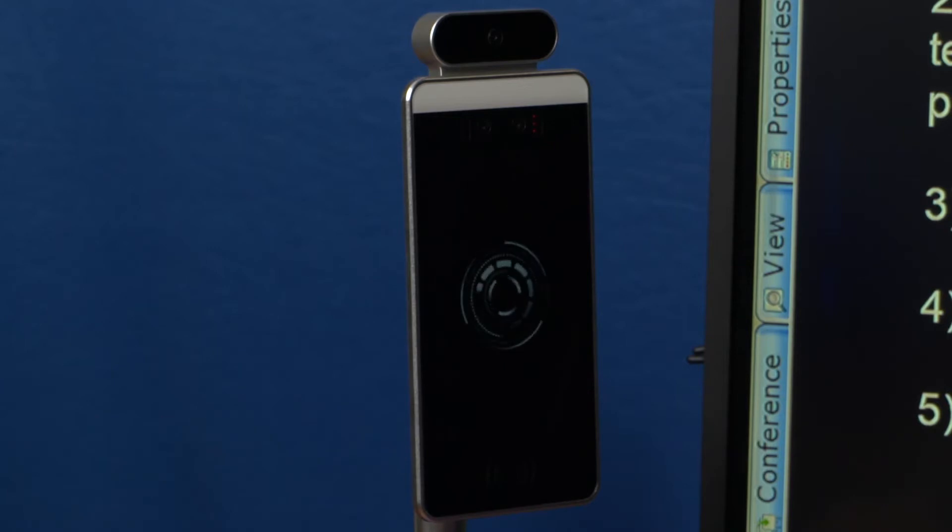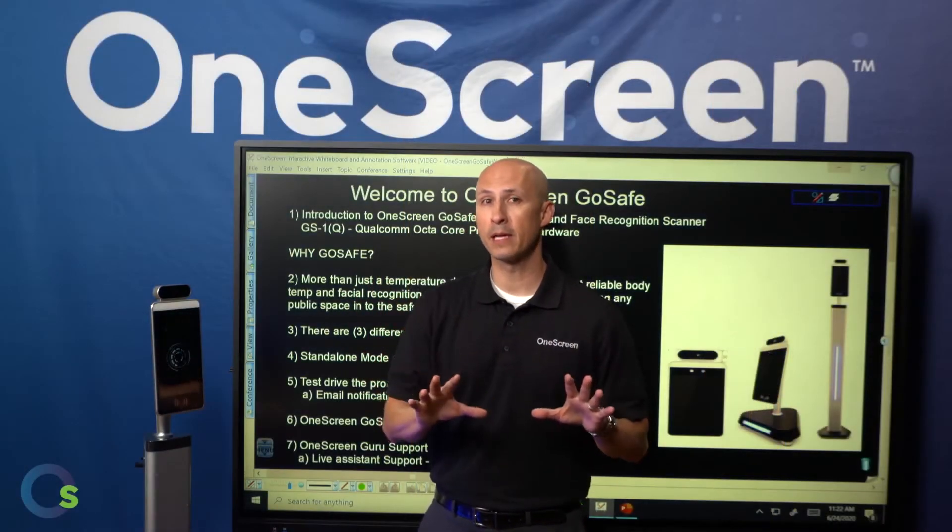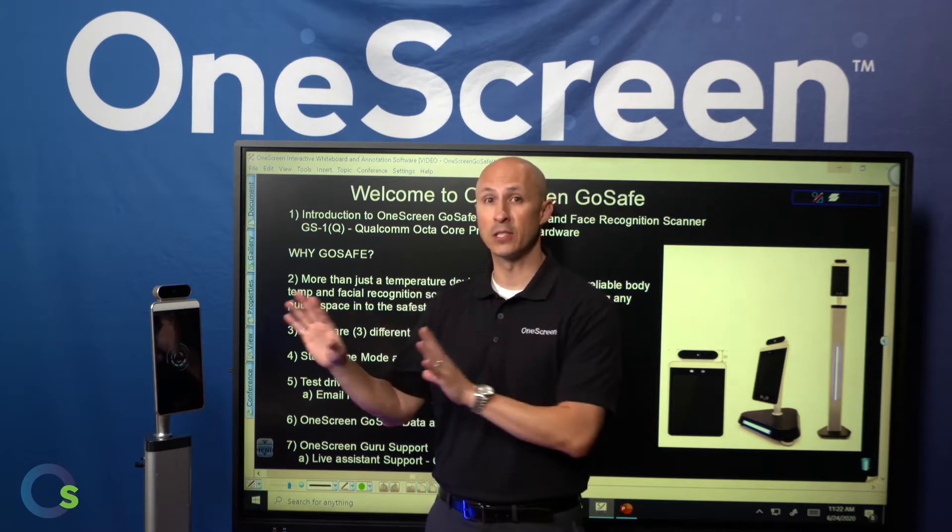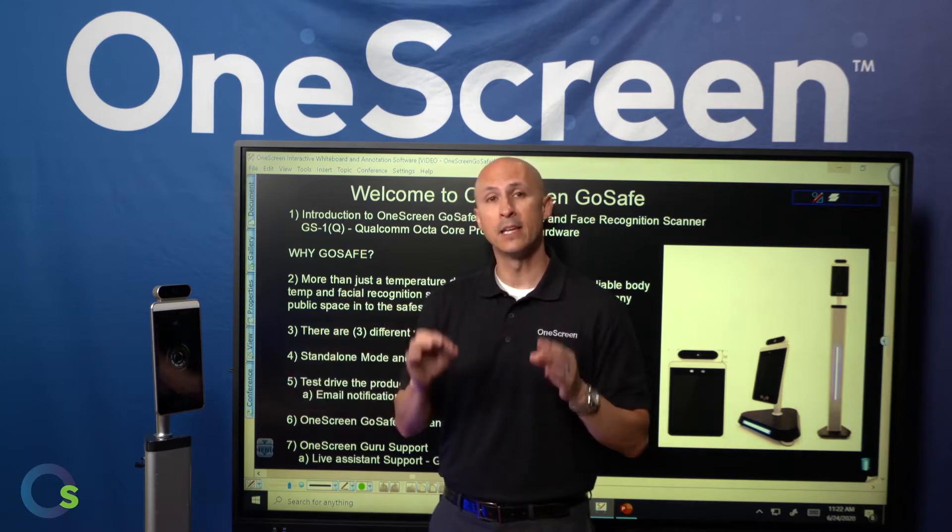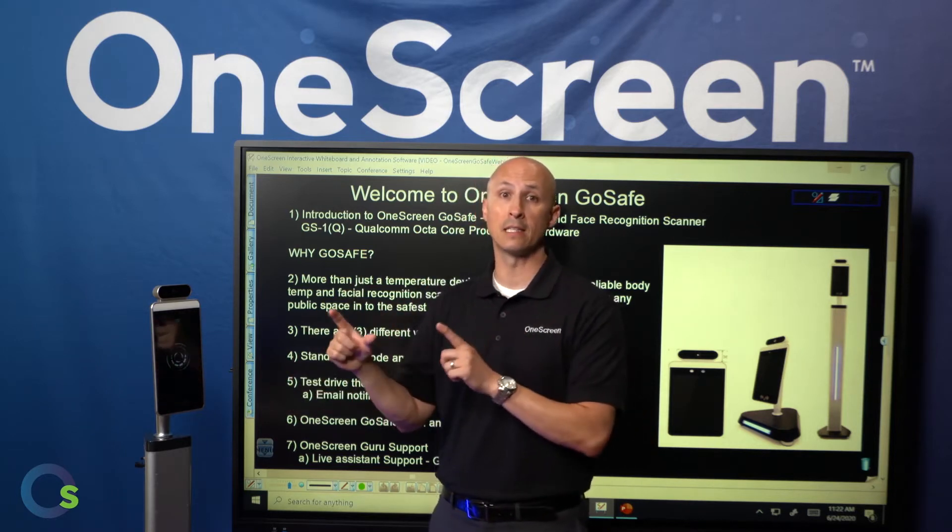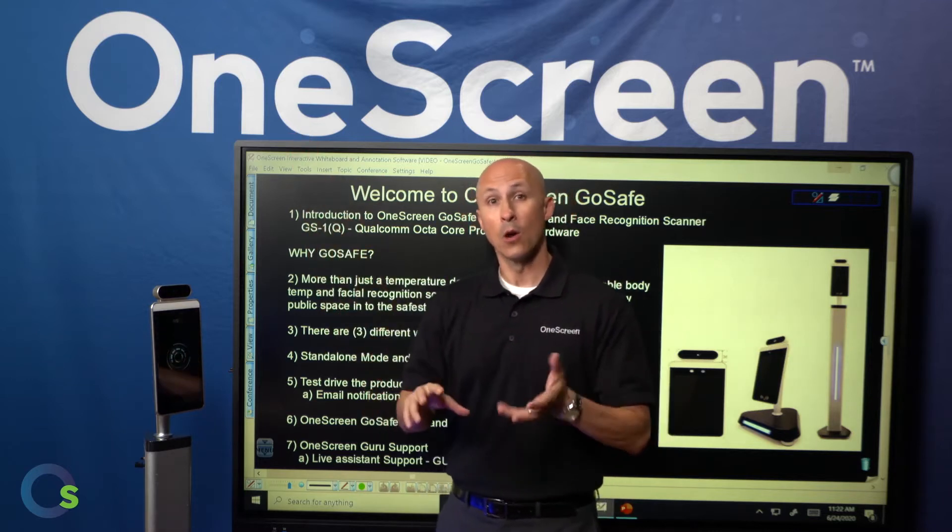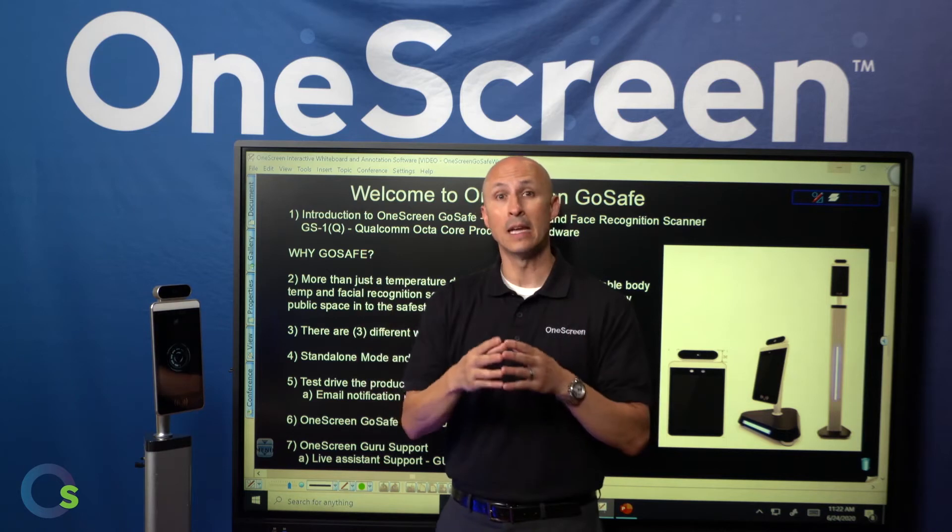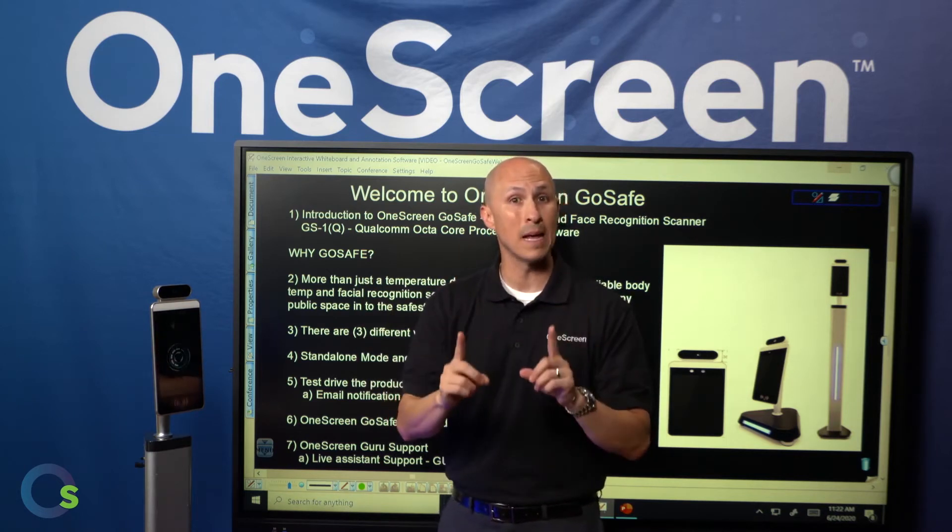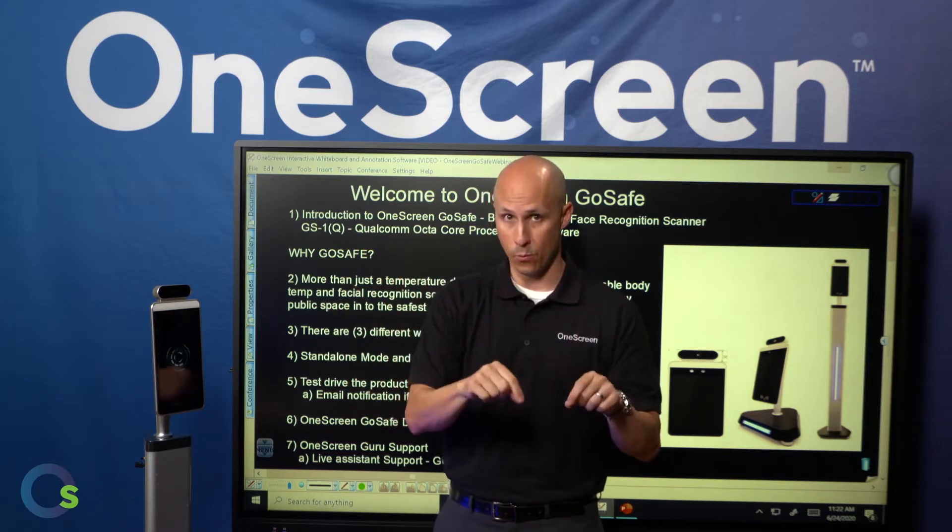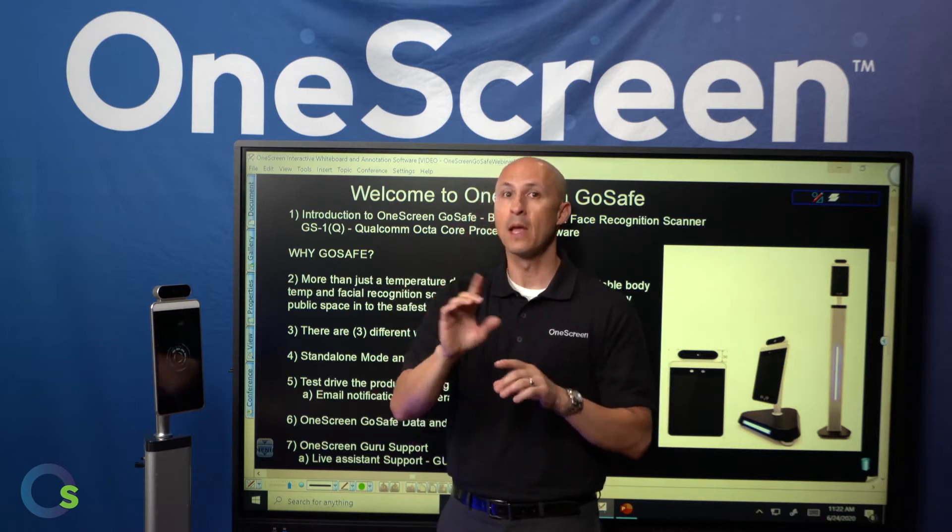Now the second way to set this up is via network mode. This is our recommended application because it gives you a lot more capability than just a standalone mode. Now in terms of setting this up, the device of course has to be powered. Additionally, you have to then have an Ethernet cable or have it connected via Wi-Fi so that it can get on your network. Now the next steps are we are going to provide you through our Guru support team the necessary software to install. Now the software does have to be installed on a Windows-based computer or Windows-based server on your network. Once that software is installed on that computer just one time, the great part is any device on your network.